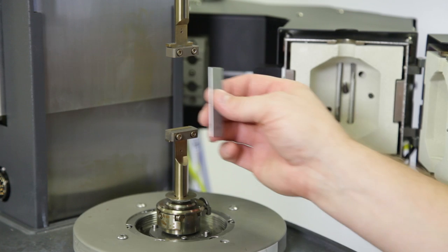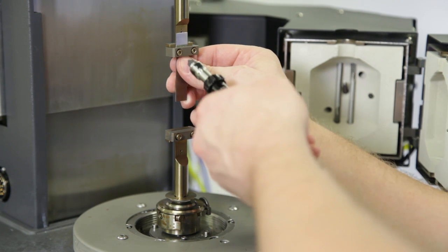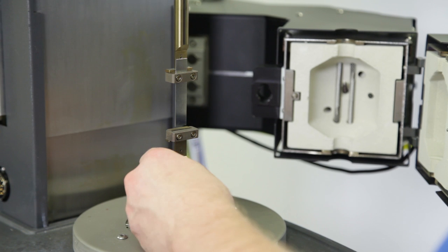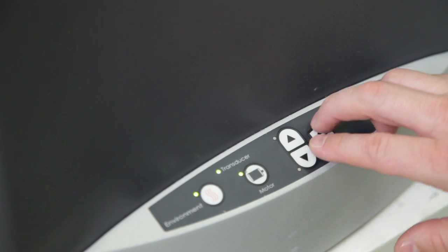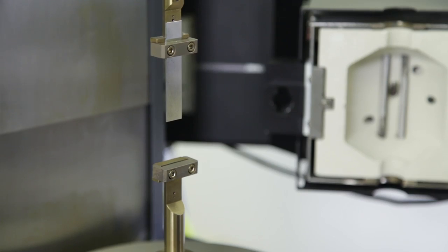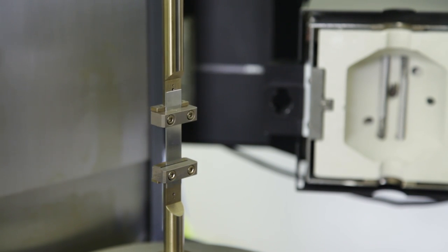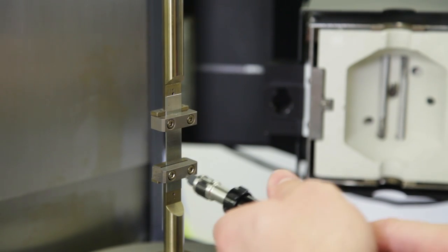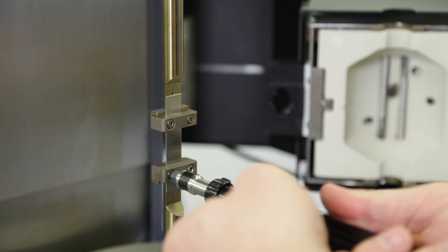Once completed, insert the alignment steel shim to the upper geometry fixture. Manually rotate the motor to align the upper and lower fixtures. Using the up and down buttons on the keypad, carefully lower the upper geometry until the steel shim is fully inserted into the anvil. Carefully tighten the screws.